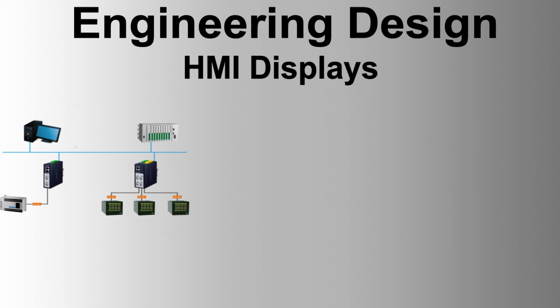Alarm configuration. Features of the DCS relating to alarm management include alarm detection, priority levels, deadband and signal filtering, suppression, and auto acknowledgement. Configuration standards should be developed for each feature to ensure consistent application across the plant. Alarm detection. Alarm detection functions for instruments are configured in the Control Station Builder. Only tags indicated in the alarm and trip listing should have enabled alarm detection functions.